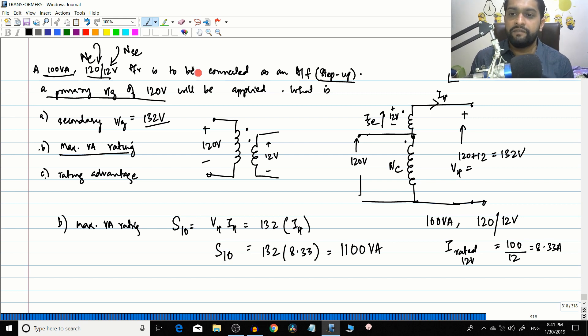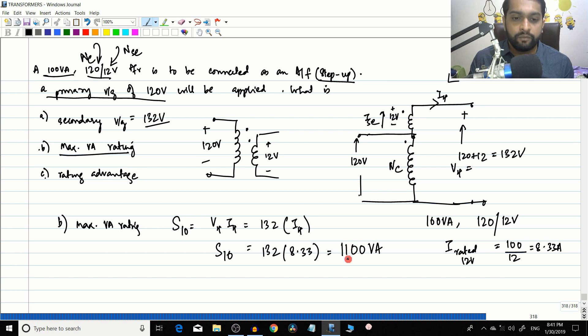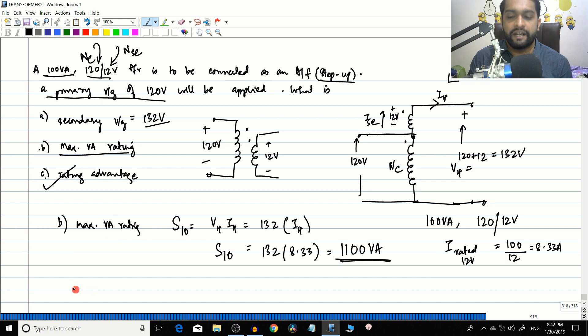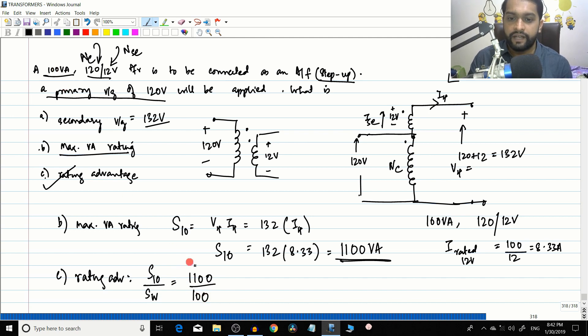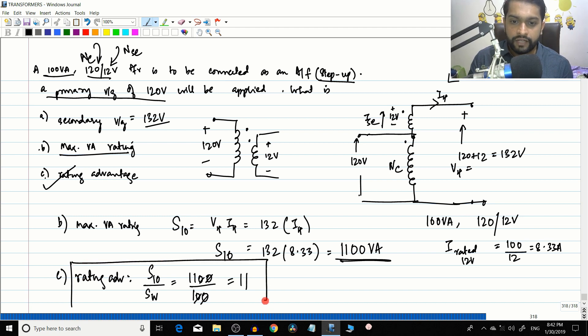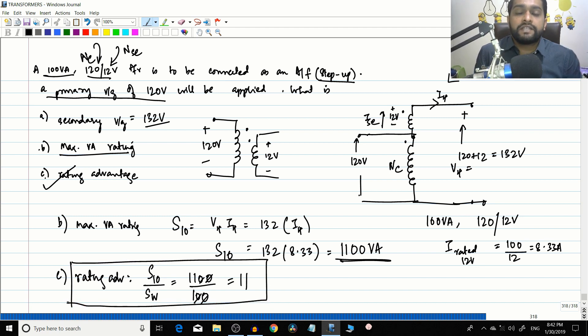So the 100 VA transformer when connected conventionally gives 100 VA, but when connected as an auto transformer it gives 1100 VA. The rating advantage is S_IO divided by SW equals 1100 divided by 100, which equals 11. The rating advantage is 11.